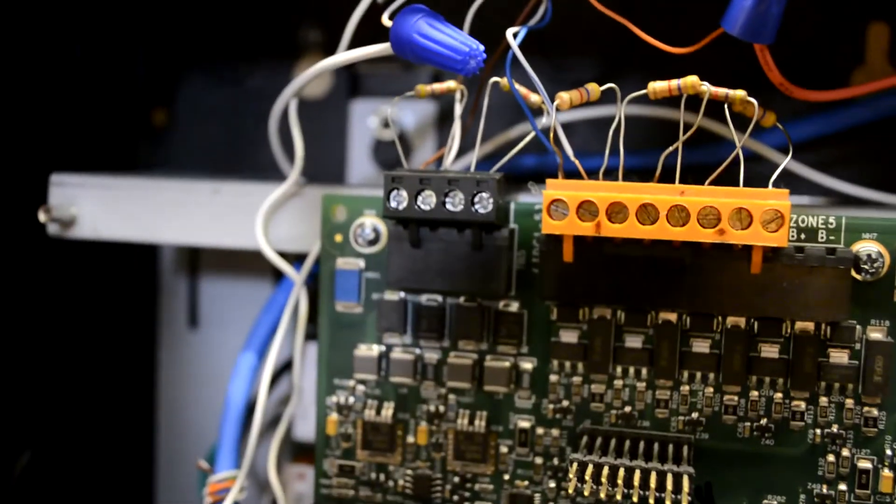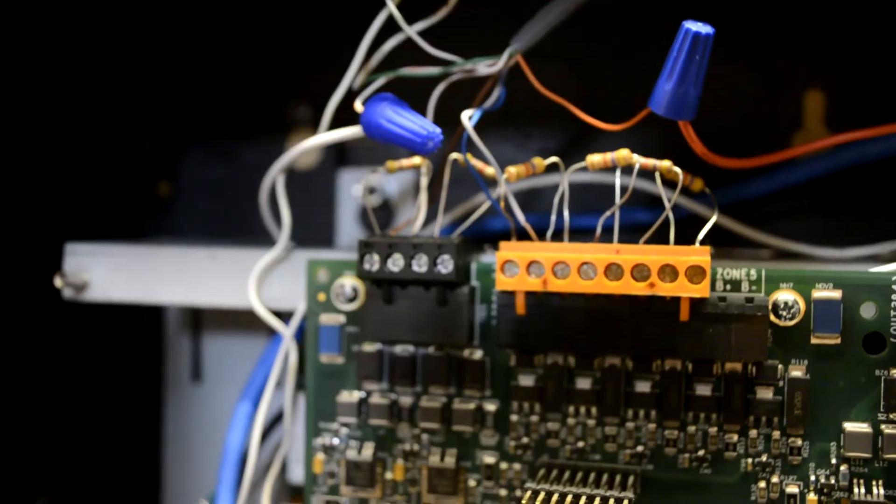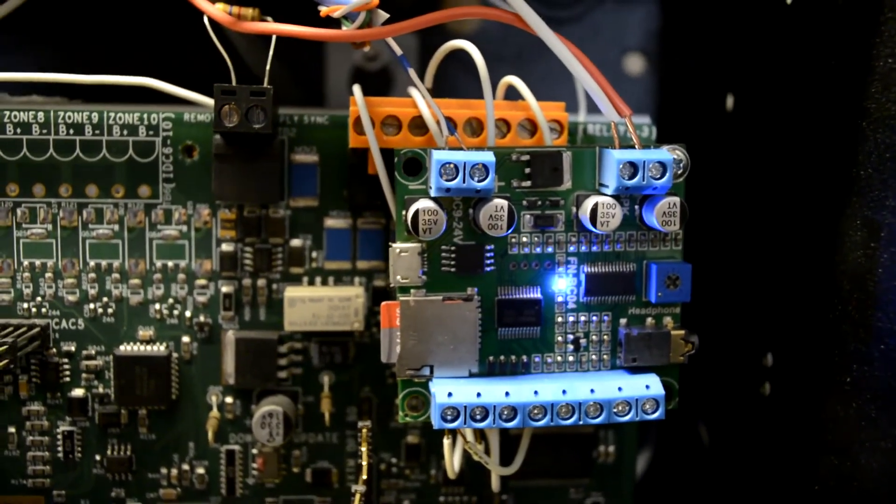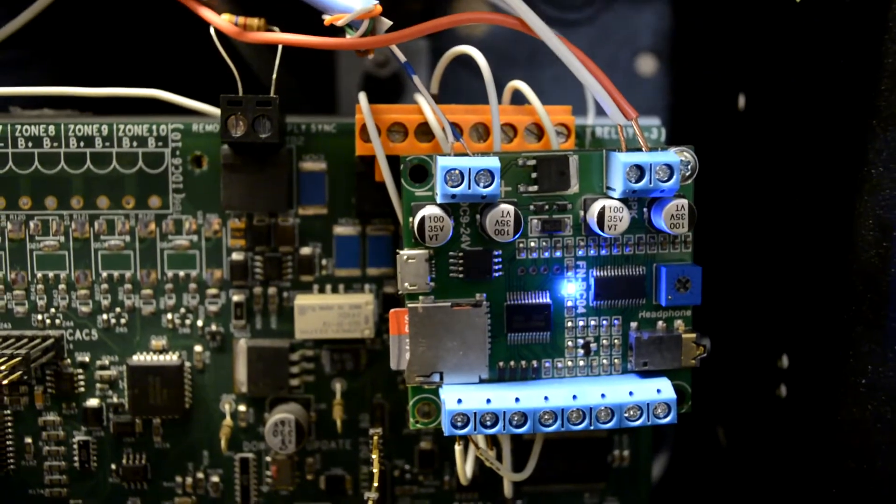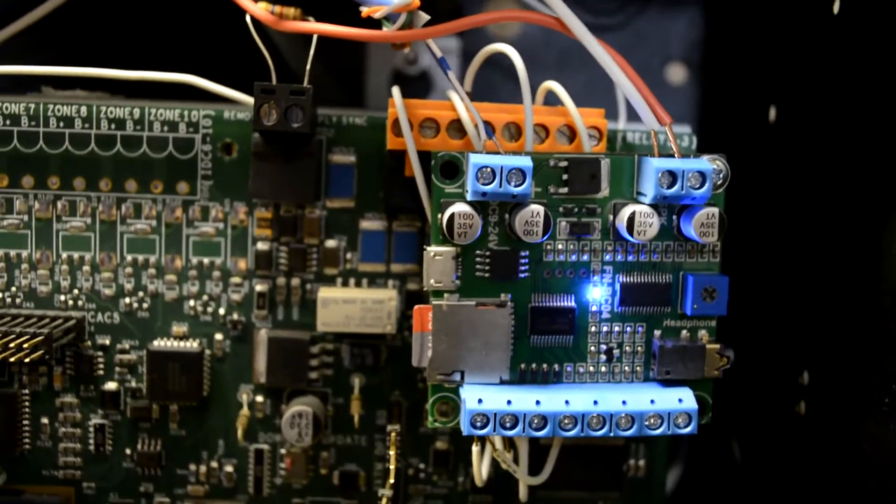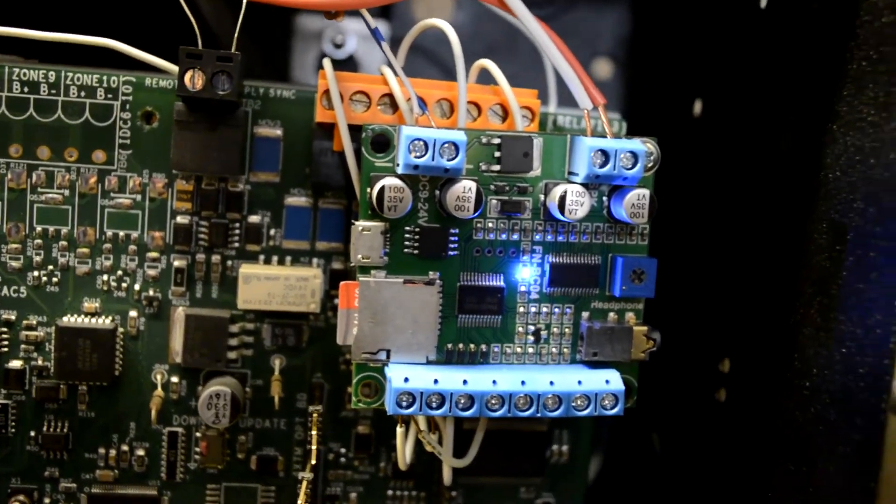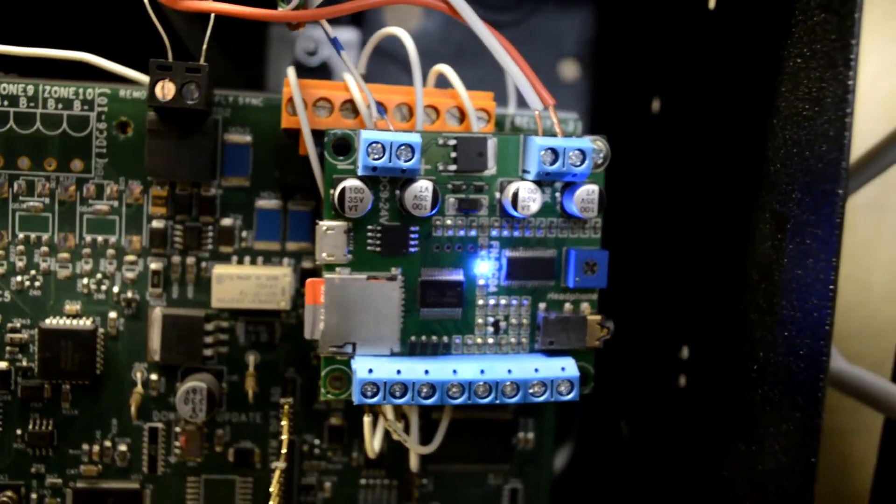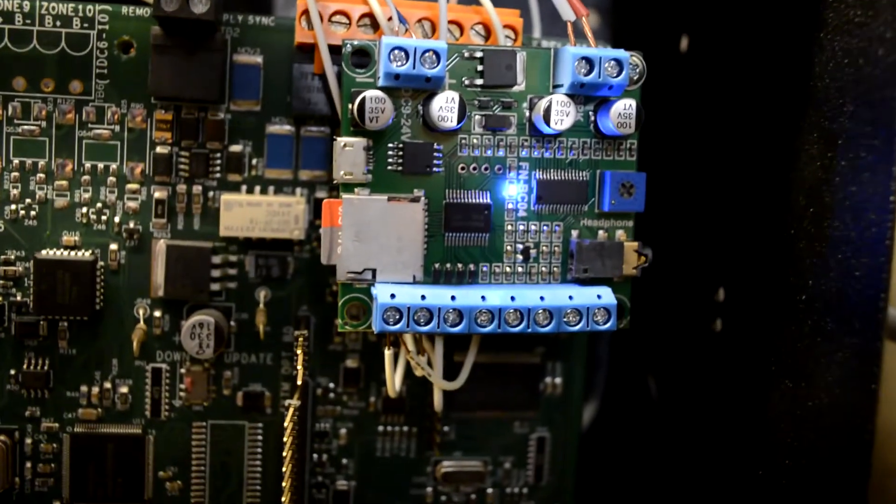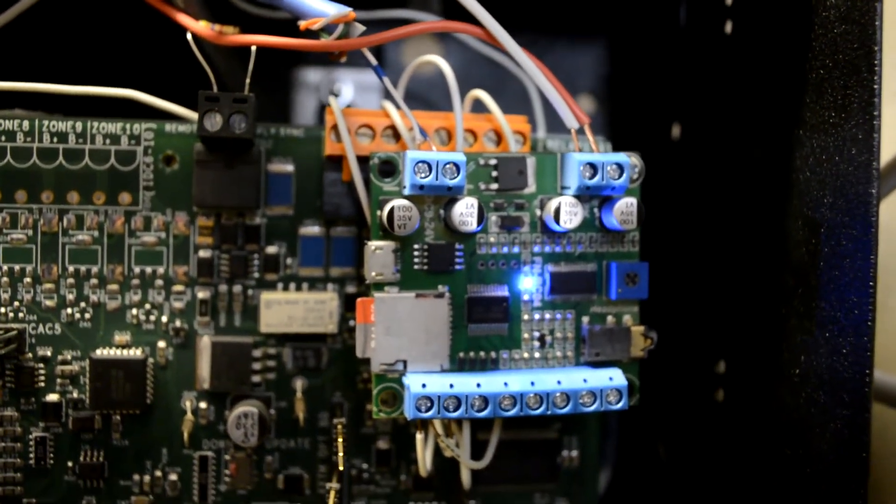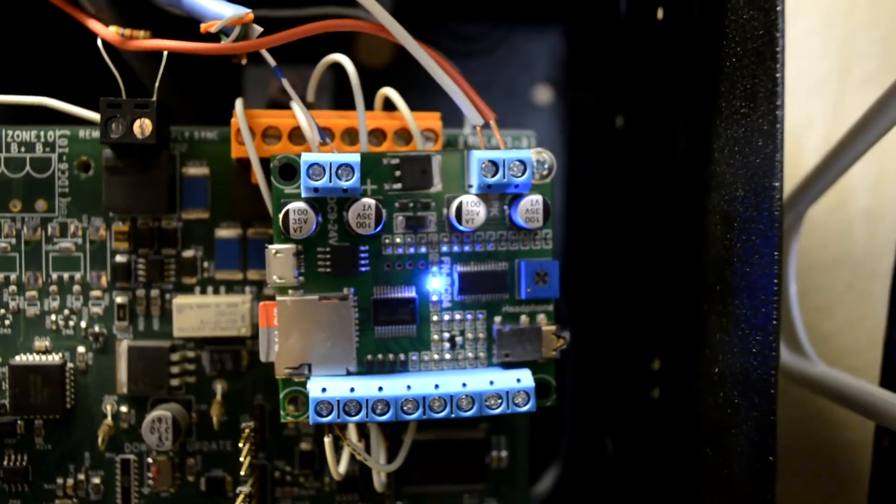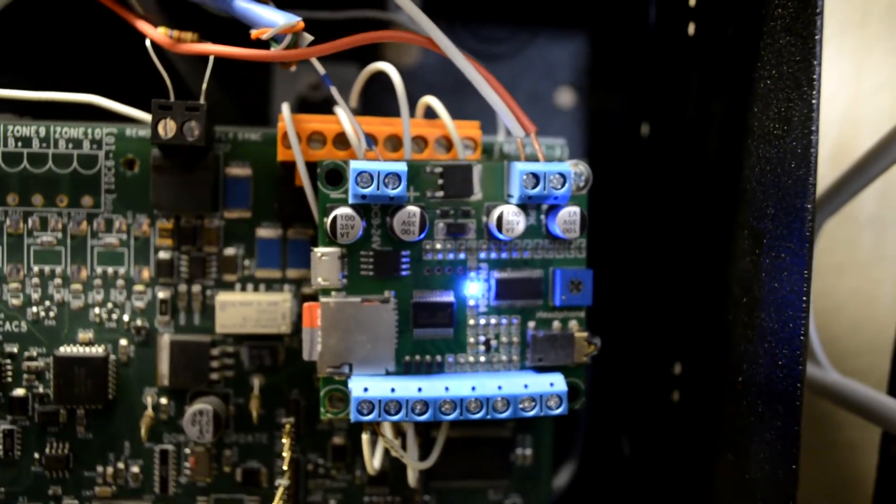NAC 2 is not currently being used, as that would just be a standard horn circuit. Now what I have noticed about this is that if you're going to be using multiple triggers, you do have to use the common from each relay. Unfortunately, you can't just wire one of the relay's commons in and expect all the relays to activate it. In my case, I had to wire the common from relay 1 and relay 2 in order to use both of them. There's a little 32 gigabyte microSD card, which is way overkill for this project. 32 gigabytes of MP3 audio is quite a bit, and for a demonstration fire alarm system it's quite excessive. But it was the only card I could find that was a decent card because Best Buy only had like 256 gigabyte cards available, and this little chip only allows for a capacity of 32 gigabytes.